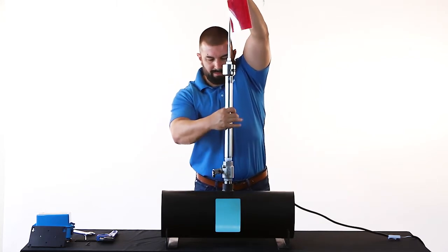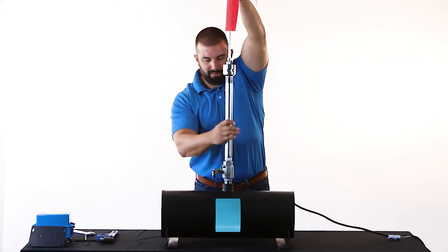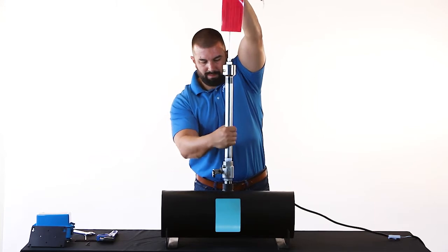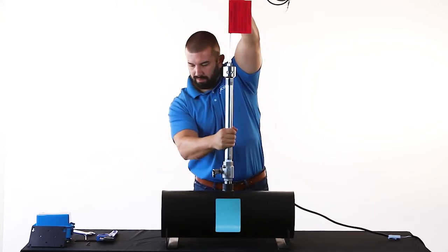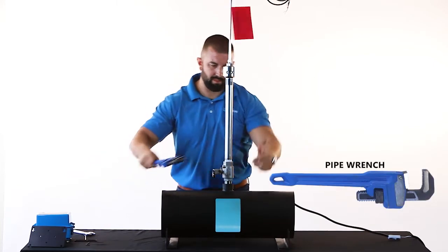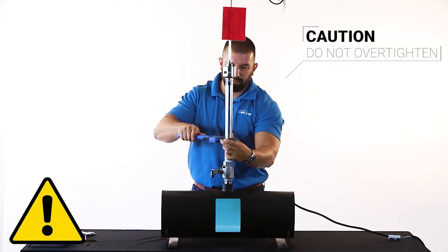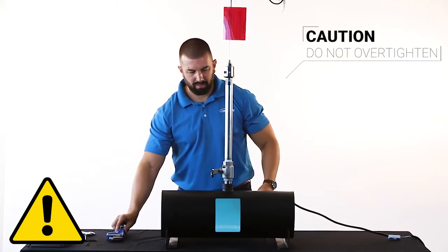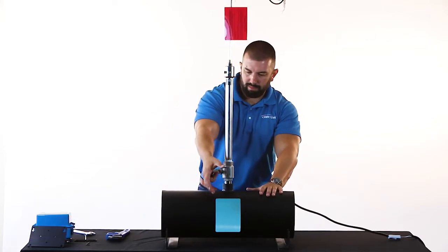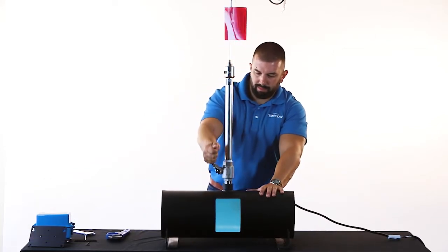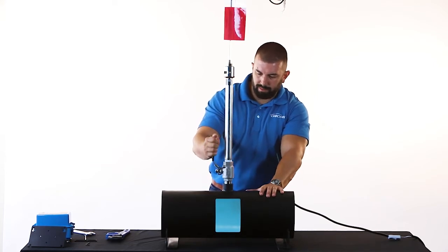Begin threading the hot tap adapter fitting into the fully closed isolation valve by hand. Use a pipe wrench to complete the installation of the hot tap adapter fitting into the valve. Be sure to tighten just enough to prevent leaks. Do not over tighten as you could potentially deform the fitting. Slowly open the isolation valve and confirm there are no leaks before proceeding.